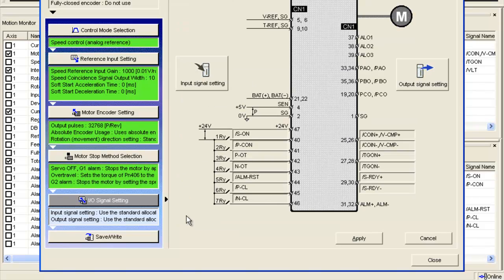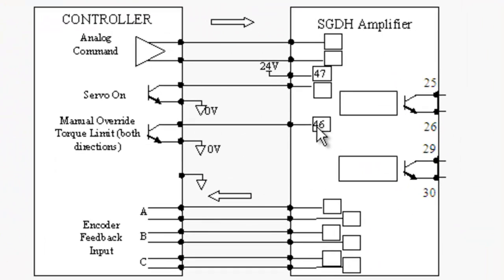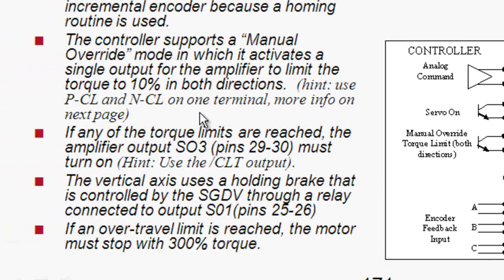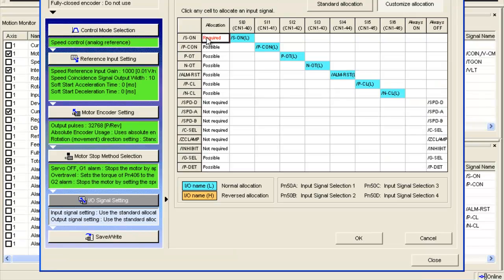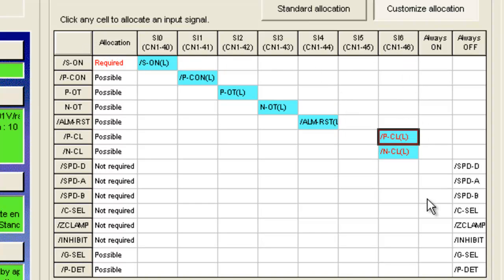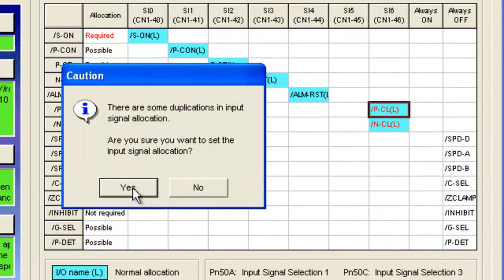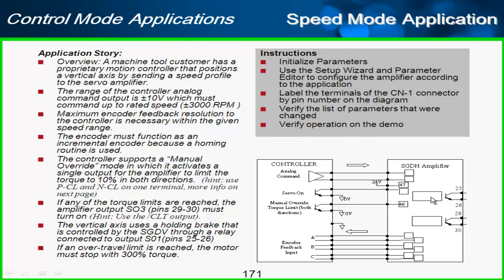The final area is the IO signal setting. The servo has an input on pin 46 for the manual override, which will be tied to PCL and NCL on one terminal. I'll go to the input signal setting and move PCL over to pin 46. It's warning me about a duplication, and I did that on purpose, so I'll click yes.